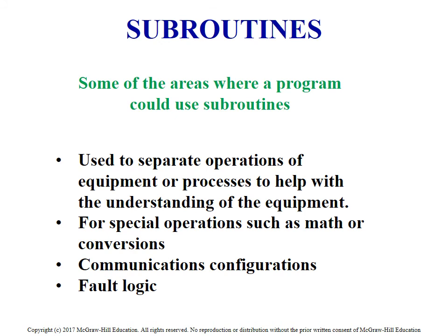Essentially, when you have a problem with a machine, it's usually the operator or someone who can point you right to the area. By putting that area in a subroutine, you're able to troubleshoot, say, 8 or 10 rungs of logic versus 10,000 rungs of logic. So that's a huge plus there.